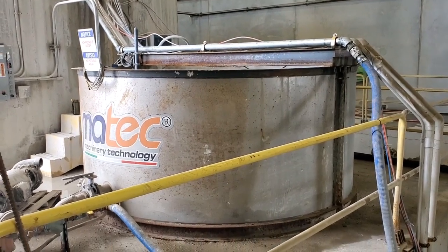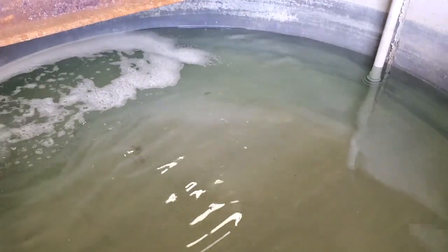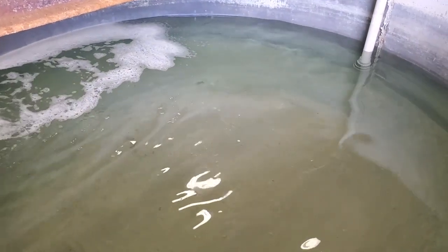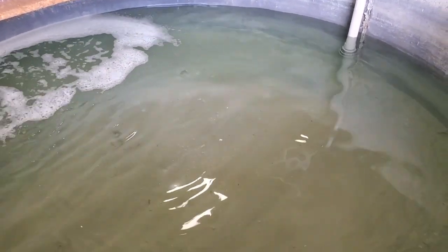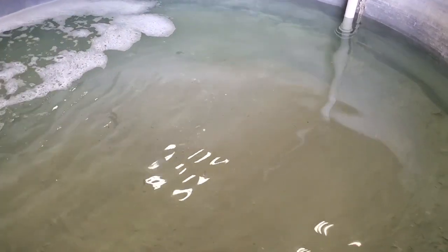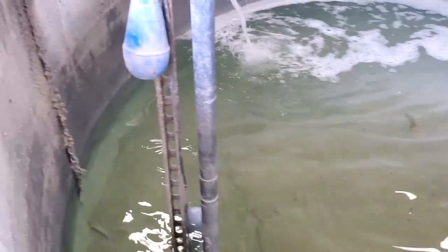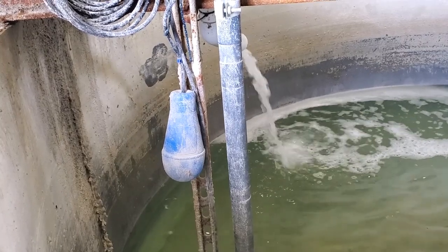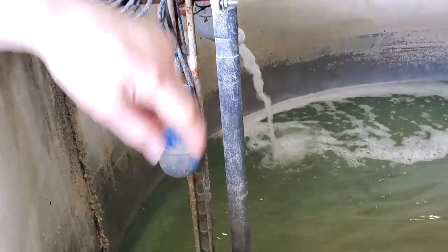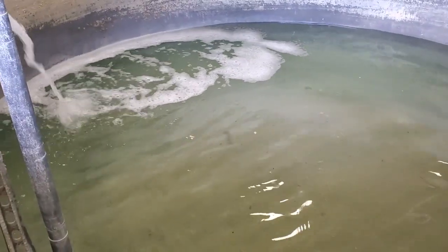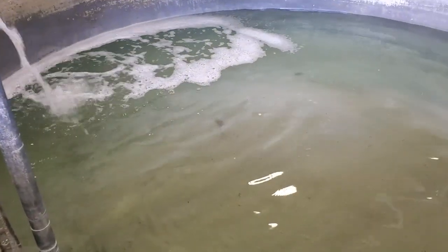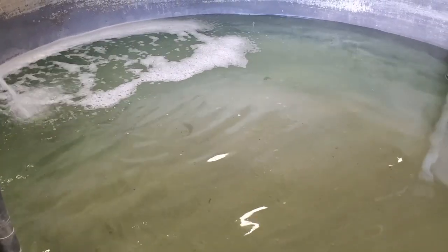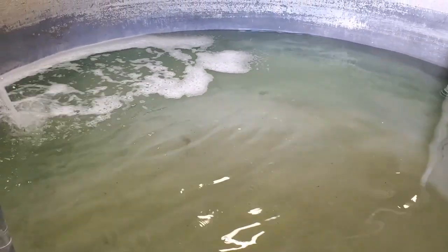All right, so let's take a look at this. Hunter and Daniel, we're looking at the tank that has the processed water left after the fines have been squeezed out of it, right? Correct. This water right now still has very high pH. There's a stream of water coming out of the filter press, and there are very few fines at this point. The water touching the water in the tank is where it's being treated. The water in the tank should be a fairly neutral pH. We try to keep it anywhere from 7 to 8.